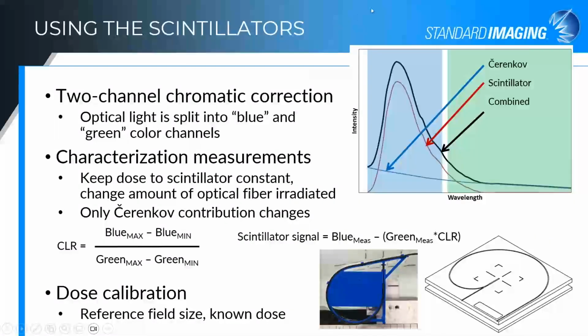The system that we use to account for the Cherenkov light is a 2-channel chromatic correction. And I apologize, I thought I had put the reference up here. I'll have to put that in the chat at the end. I'm blanking on the name right now, but there's a published paper, and we can follow up with that if you want, on the 2-channel chromatic correction, where our scintillator is a blue scintillator. And the Cherenkov light is a broad spectrum contaminant.